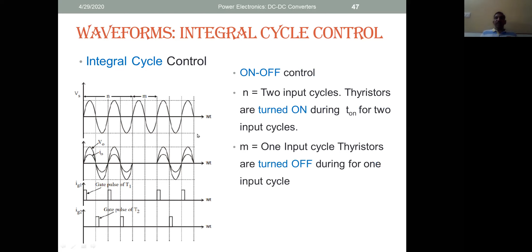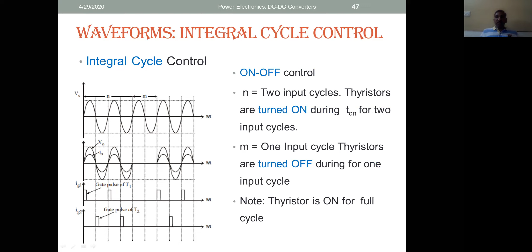Here, no triggering, so nothing is turned on. Again, trigger pulses turn on for 2 cycles, meaning feed for 2 cycles, don't feed for 1 cycle. Likewise, you get control over an integral cycle, meaning you can either supply it fully or not - N number of input cycles during which the thyristor is turned on, and M during which it is turned off, for the full cycle.